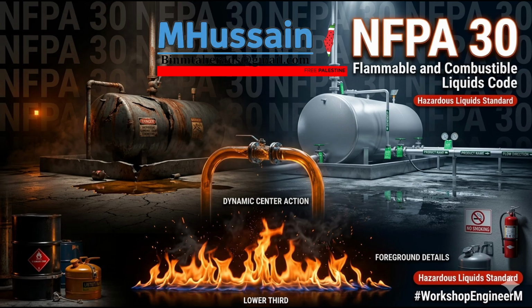And critically, they have to be situated far away from any building HVAC intakes. If an adjacent office building's ventilation sucks in the massive vapor plume expelled by an emergency tank vent, you've just pumped a highly explosive, pre-mixed fuel-air payload directly into an occupied space. The routing of the invisible vapor is as critical as the welding of the steel tank.